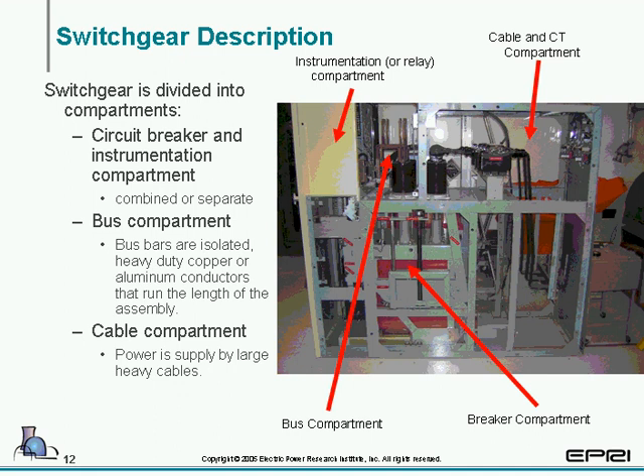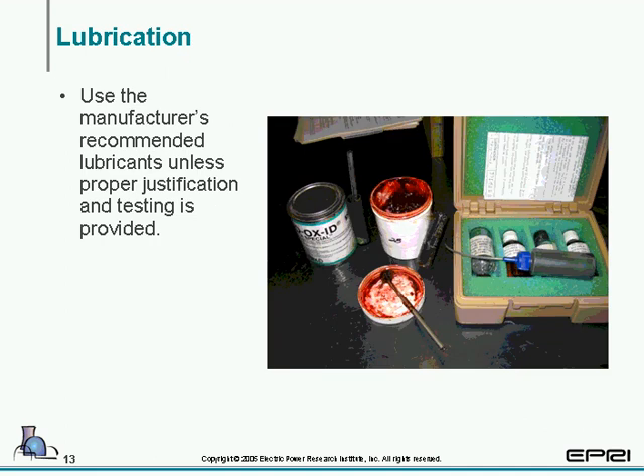On some lower voltage and most medium and higher voltages, this bus compartment cannot be seen. It is protected by a steel barrier or an isolation barrier. And then the last one we have is the cable compartment, which is normally in the back of the cubicle. So if you open up the back of the cubicle, you would see the cable compartment, but not necessarily see the bus compartment.